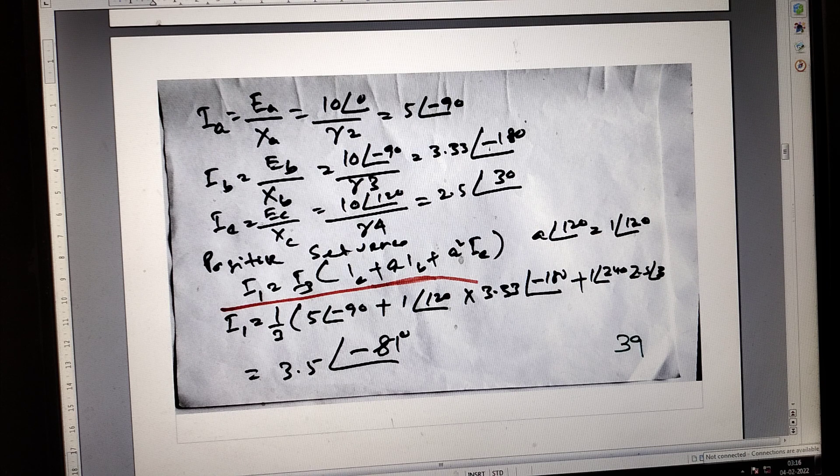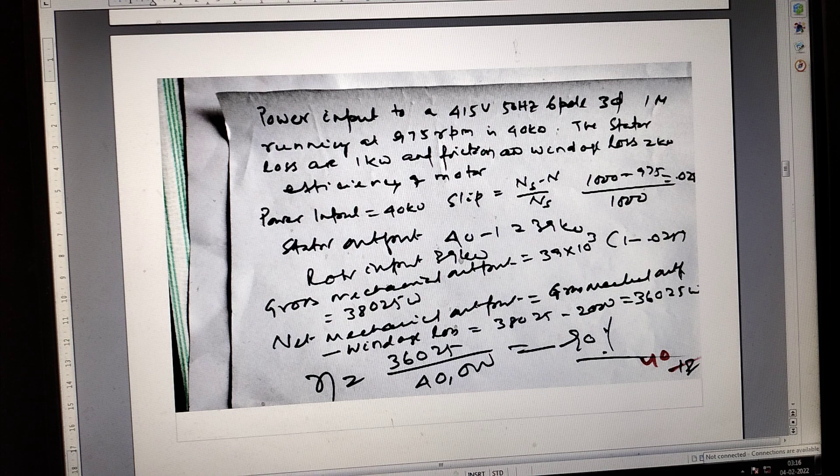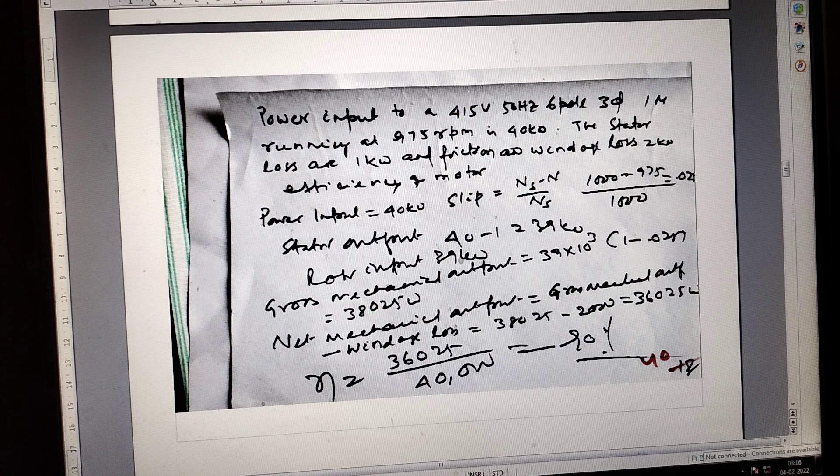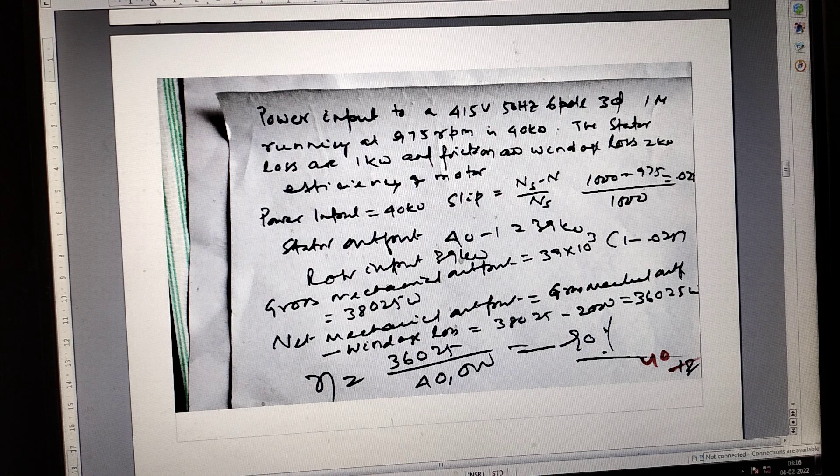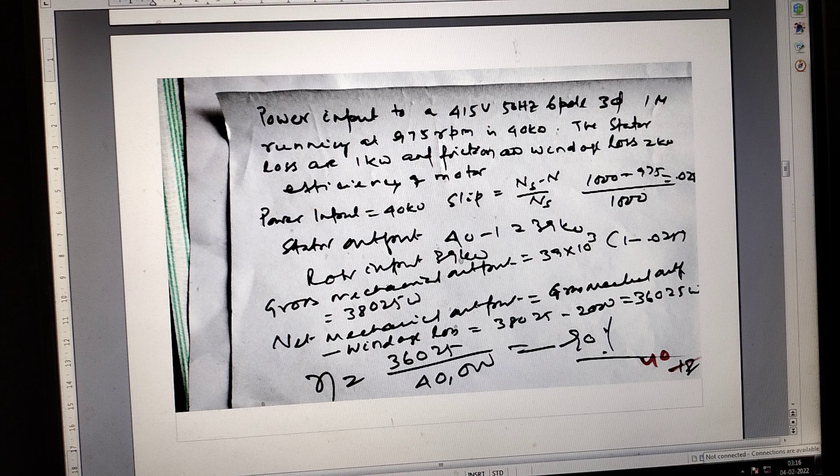Here the power input for induction motor: after stator loss, stator output equals rotor input, and gross mechanical output equals rotor input times one minus slip. It's 39 kilowatts times one minus slip.